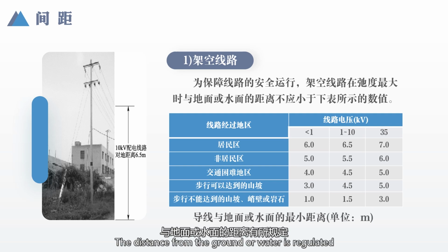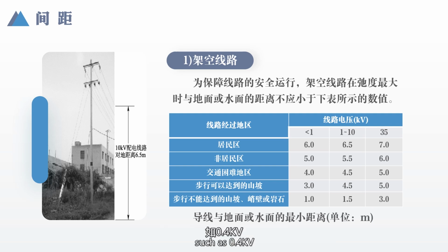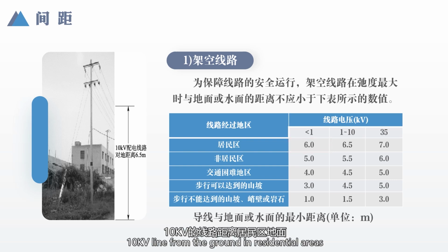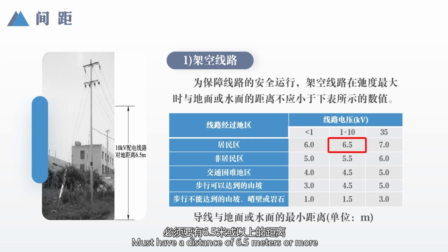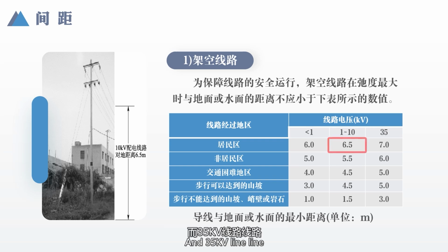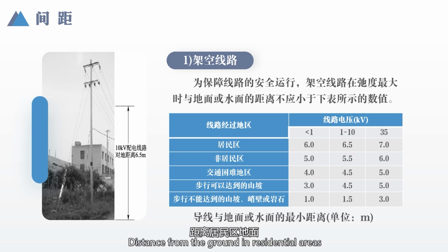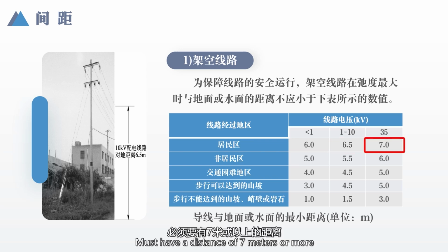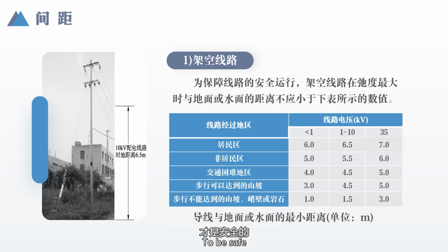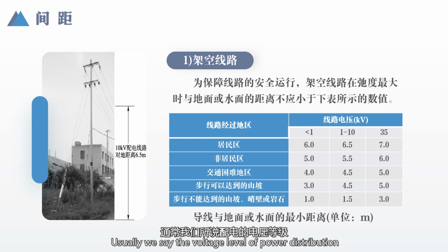To ensure the safe operation of the line, the distance from the ground or water at the maximum sag of overhead lines is regulated. For example, a 0.4 kilovolt line, that is, what we call a 220/380 volt line, must be 6 meters or more from the ground in residential areas to be safe. A 10 kV line must be 6.5 meters or more from the ground in residential areas to be safe, and a 35 kilovolt line must be 7 meters or more from the ground in residential areas to be safe. These 3 voltage levels are what we usually call the voltage levels of power distribution.